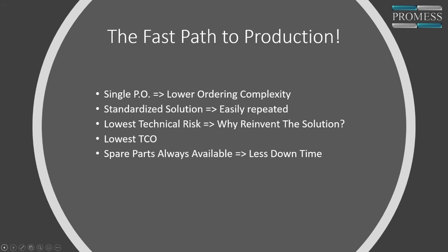So yes, we've done that in the past using our other systems, like our press system, and using positional feedback into our controller. We can calculate shim height and what shim needs to be used so that it can be put into the assembly process and retested. So hopefully that answers your question. Yes, it can be done.